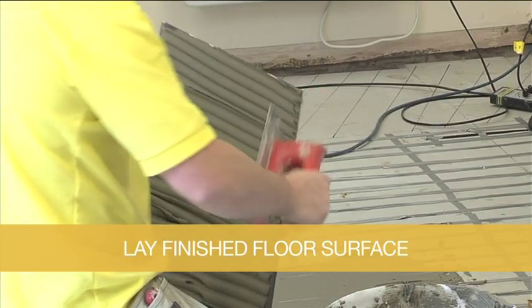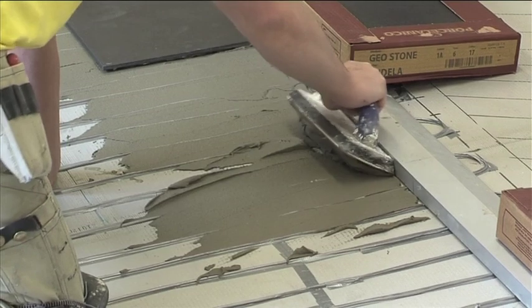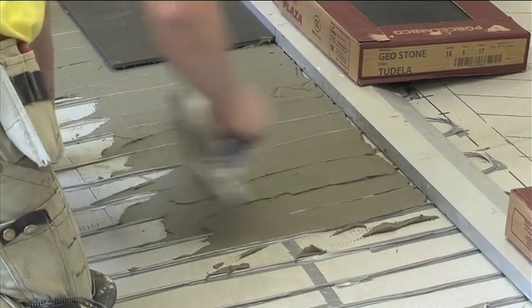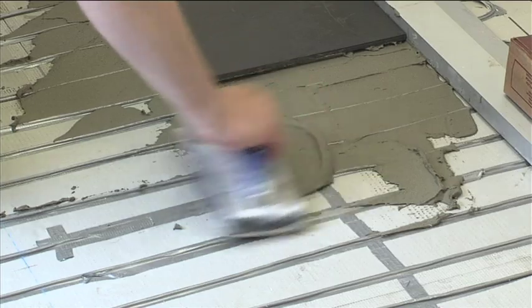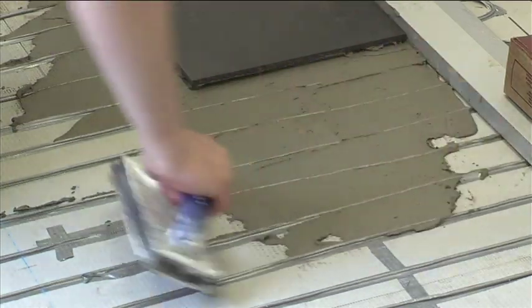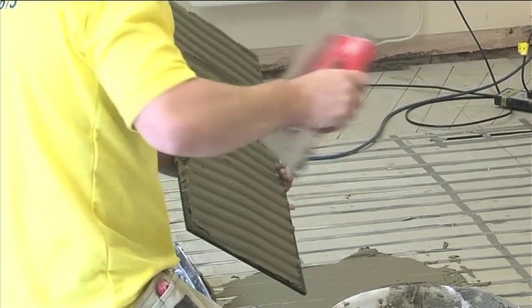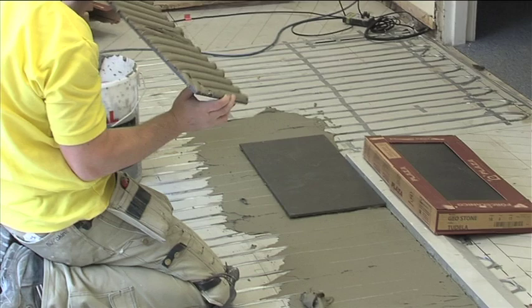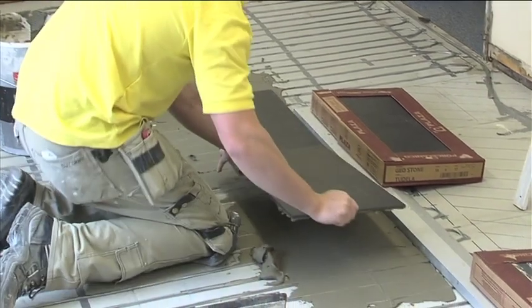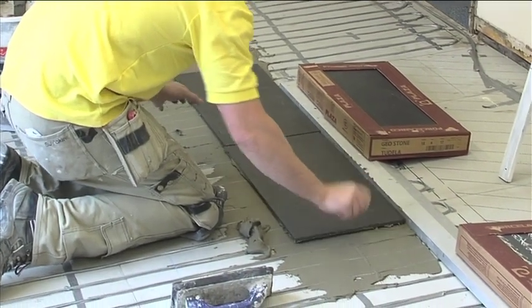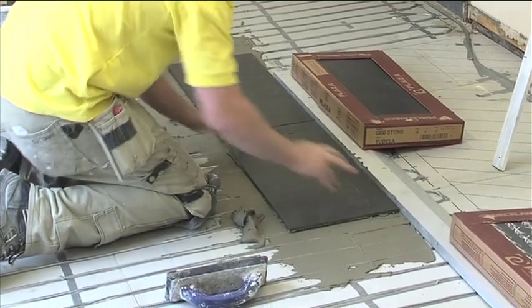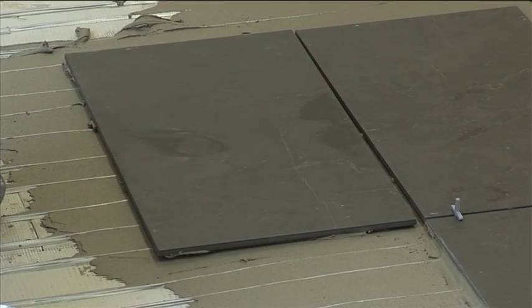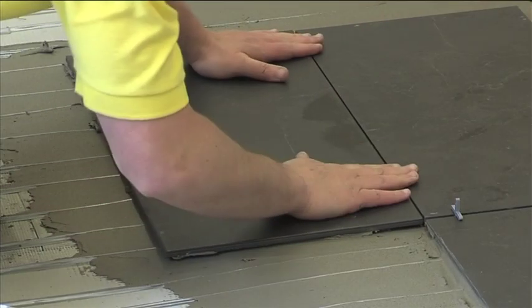Tile as normal using flexible tile adhesive. Gently comb the adhesive in the direction of the cable runs using a rubber back trowel to minimise the chance of dislodging the cable. Use a notched plastic trowel if possible. Take care not to allow the trowel to come into contact with the heating cable when applying the adhesive. Use sufficient adhesive to ensure that no gaps or voids are left under the tile.